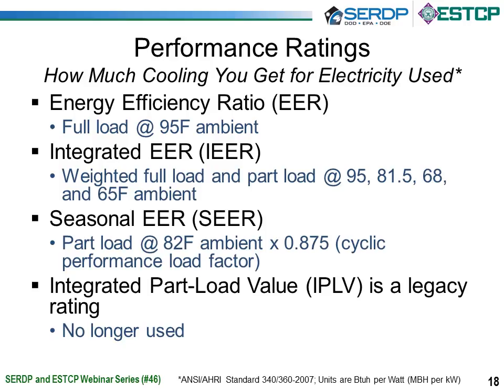Those first 2 are usually the main ones you see with commercial equipment. The next 2 I just put here for the sake of completeness. The seasonal SEER is usually for smaller equipment, 5 tons and under, usually residential or small equipment. And the IPLV is an older rating that you might see, but it's no longer used. It's similar to the IEER.